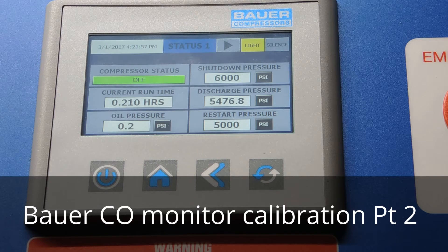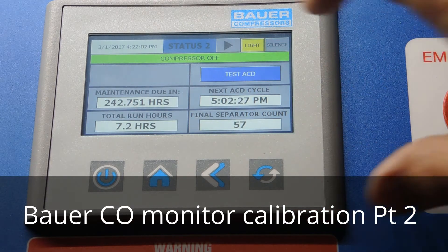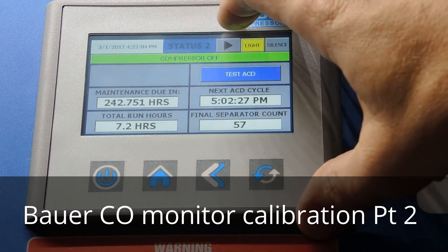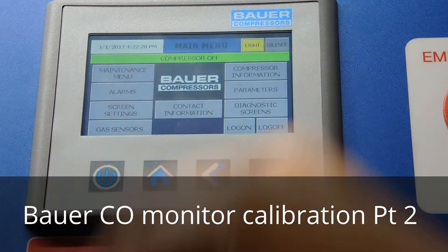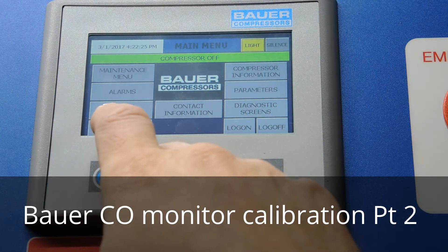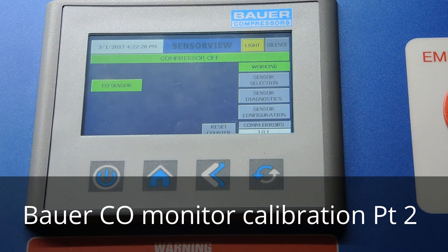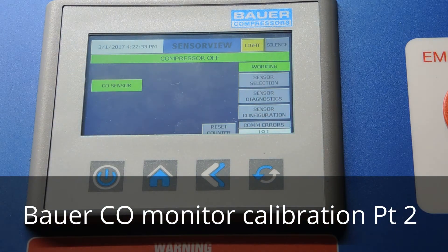We're going to start the calibration procedure. When you hit the arrow key above the status it gets us over to the main menu, which has quite a bit of information. This video is only going to cover how to calibrate the CO monitor — we'll have other videos for the rest. So we press the gases button and notice that the sensor view program shows the CO sensor is working.